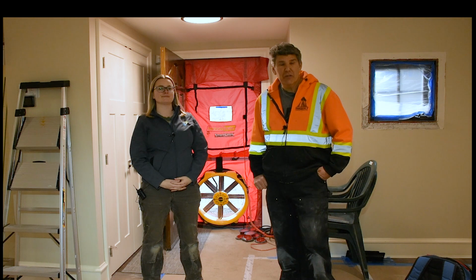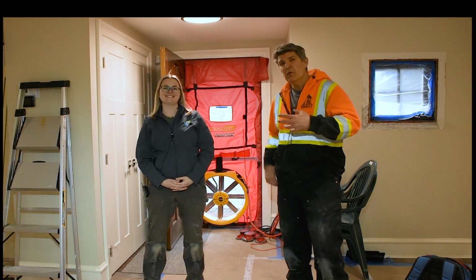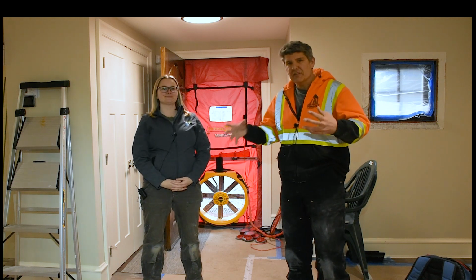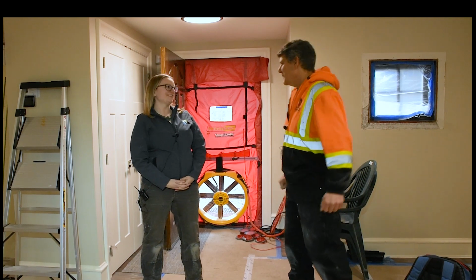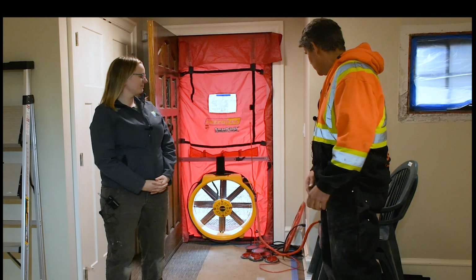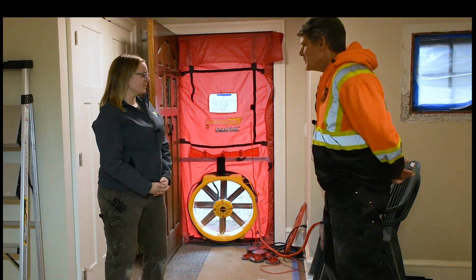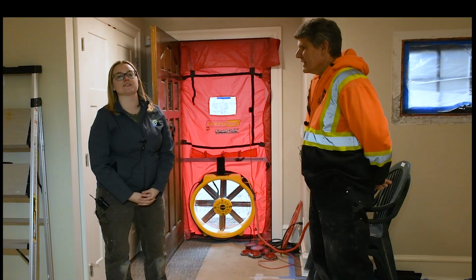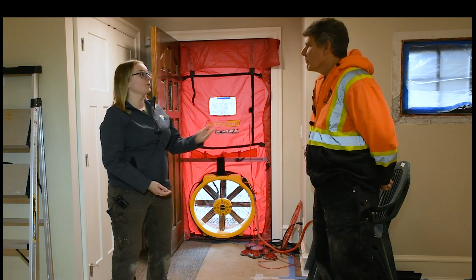All right. Today we're out here at our Fort Langley Homes Deep Energy Retrofit. And I'm here with Emma from E3 Eco Group, who's been involved in doing the fan door test, our pre-test of this home, as we prepare it to go through a deep energy retrofit. How you doing, Emma? Doing great, thanks, John. Good. Tell me what we found here with the fan door test, and maybe explain what you've been doing. So with my blower door test equipment, I can test the original air tightness of this home. That is the baseline of the air tightness from which we want to improve.